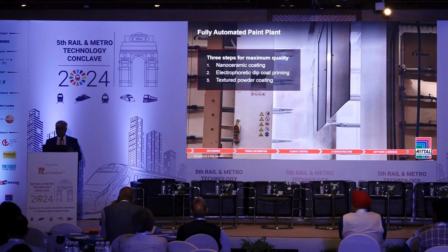These are some of the tests which we call routine tests. I'll give you information about one test, which is the mechanical resistance of the paint, not the sheet steel. These are some of the tests we do to check the reliability of the paint. I'll explain the Erichsen cupping test, in which a metallic ball is pressed onto a painted surface to check whether the paint is cracking or not.